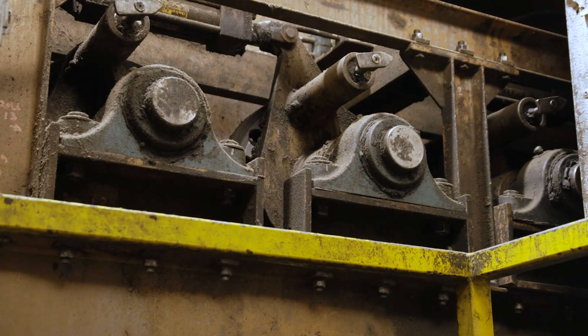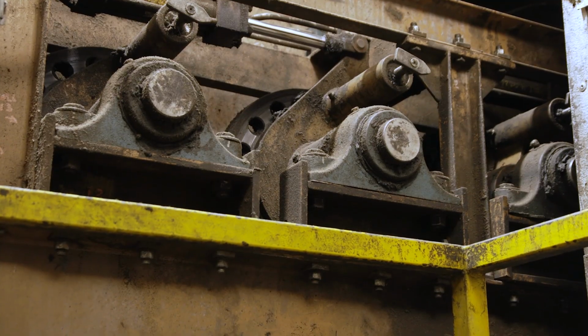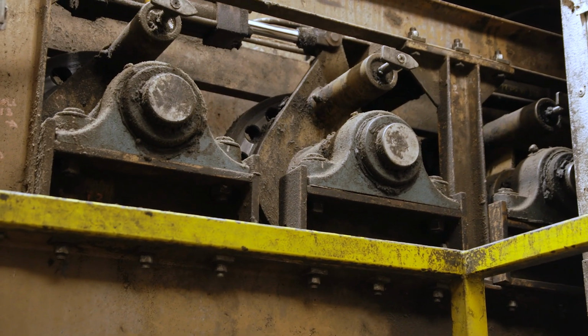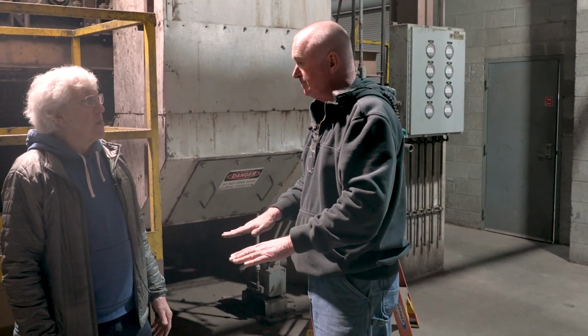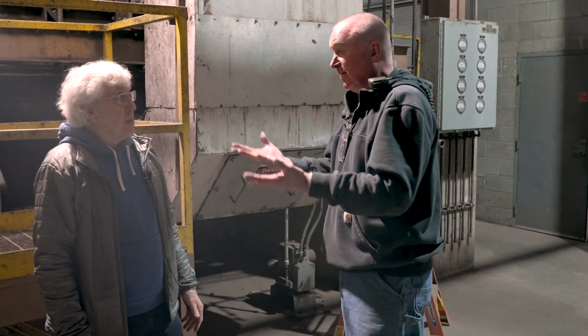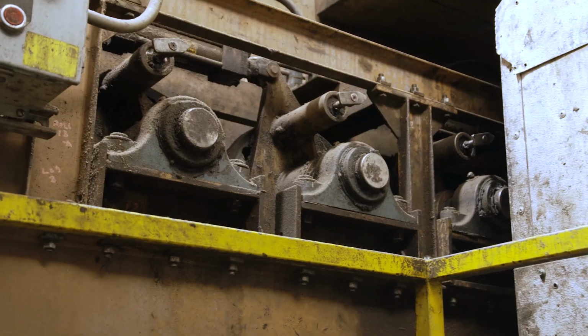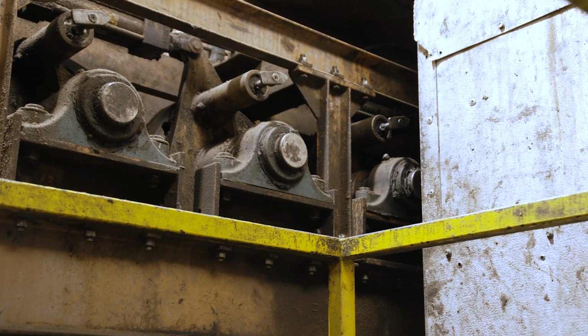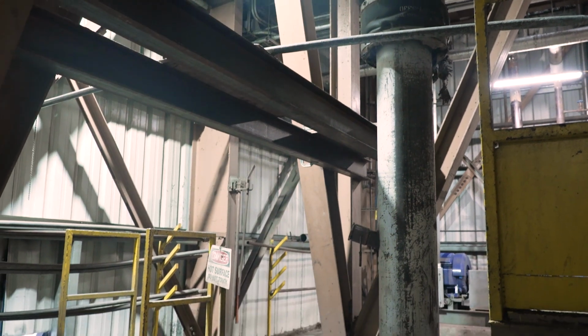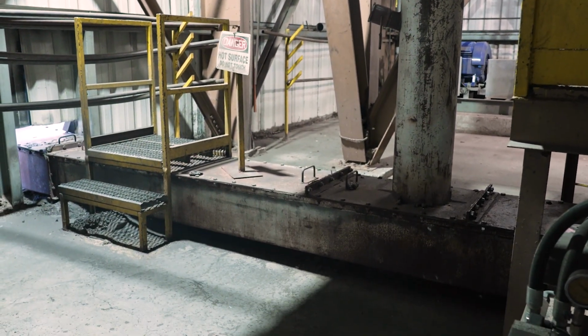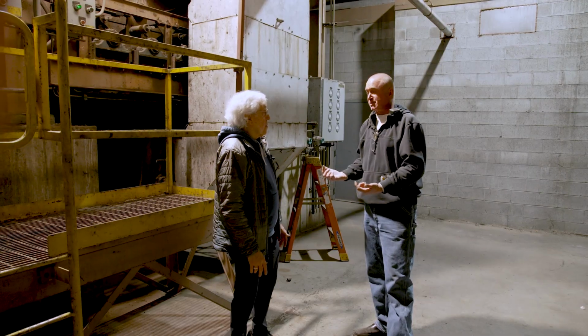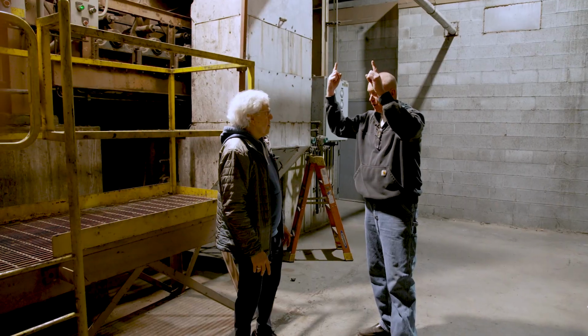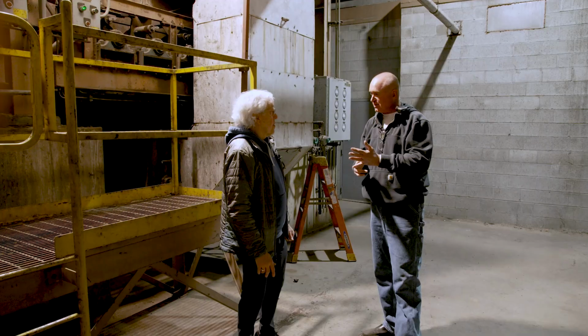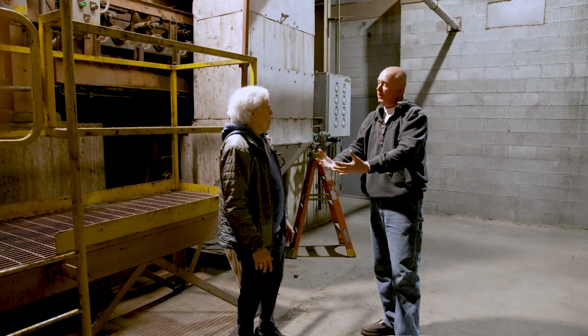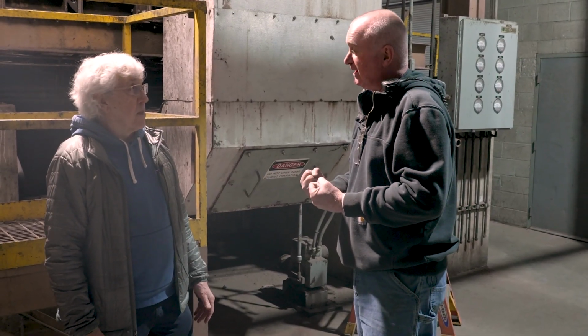The grate rolls are on a timer. The operator sets up a timer as to how often they roll. That's how he controls his fuel bed depth. When the grate rolls roll, the inert ash goes through the grate rolls into the main ash transfer conveyor and out to the ash collection system that we can talk about later. The heat from the combustion process, flue gas is what we call it, travels up into the upper furnace where it heats the water in the water wall tubes, passes through the convection section, the superheater, where we heat the water and turn it into steam.